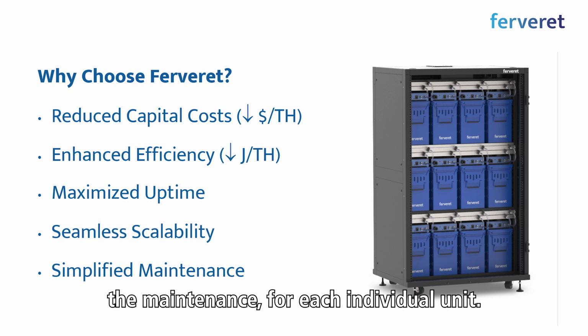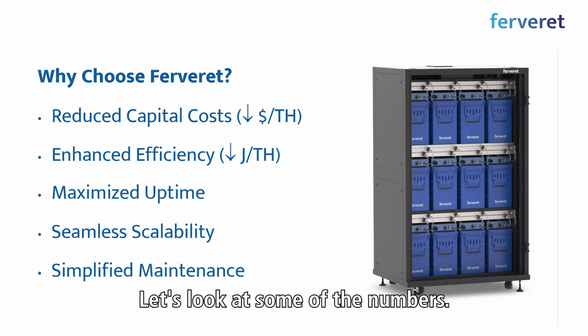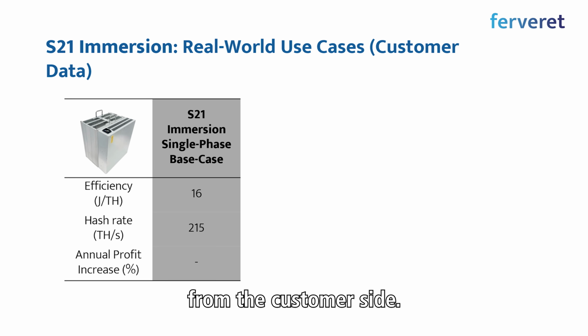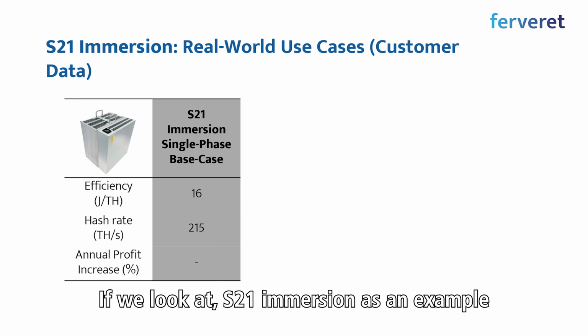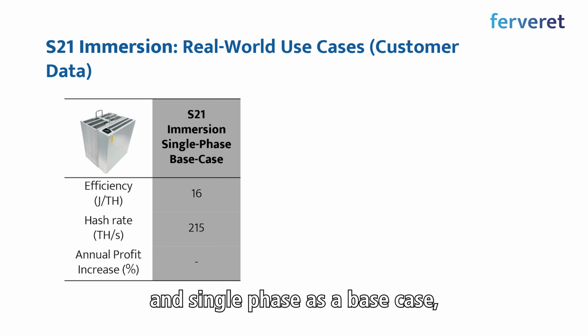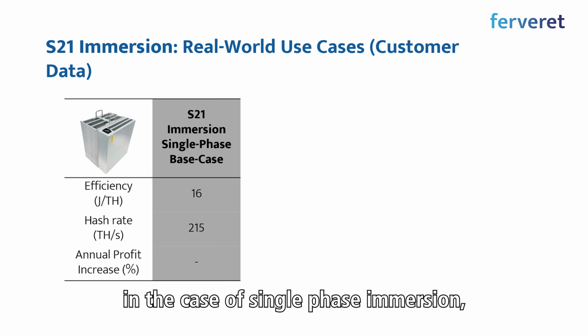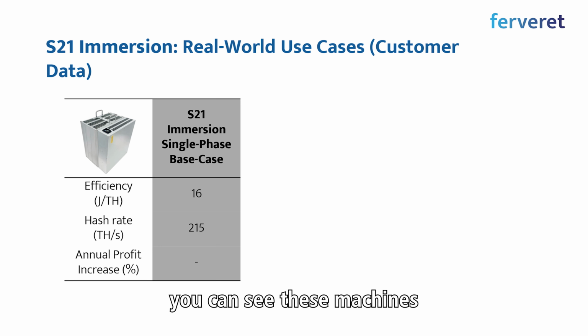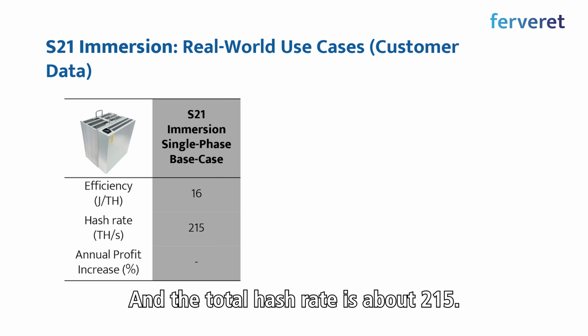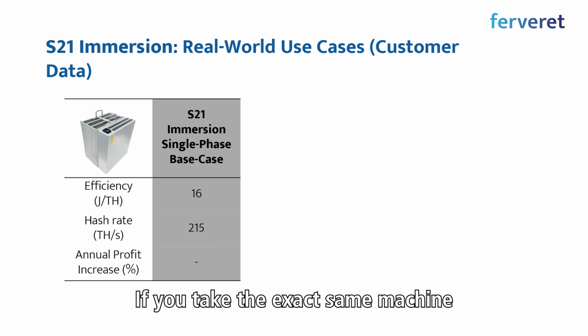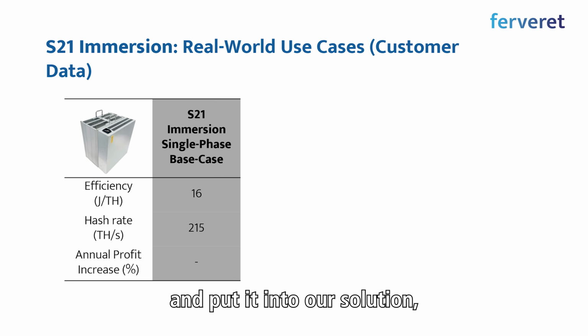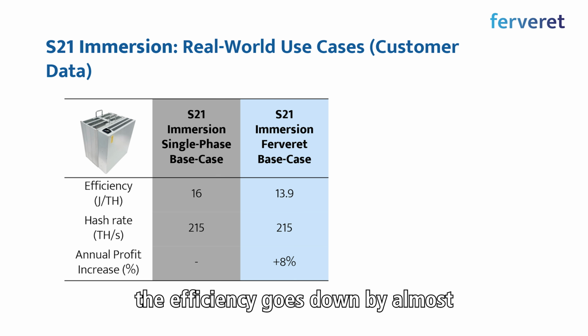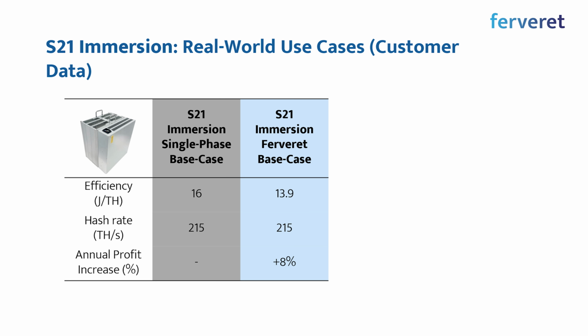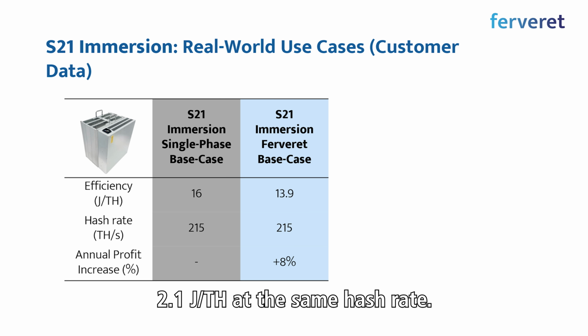Let's look at some numbers — this is real data from a customer. Taking the S21 immersion as an example with single phase as the base case: in single phase immersion, these machines run at an efficiency of 16 joules per terahash, with a total hash rate of about 215. If you take the exact same machine and put it into our solution, the efficiency improves by almost 2.1 joules per terahash at the same hash rate.